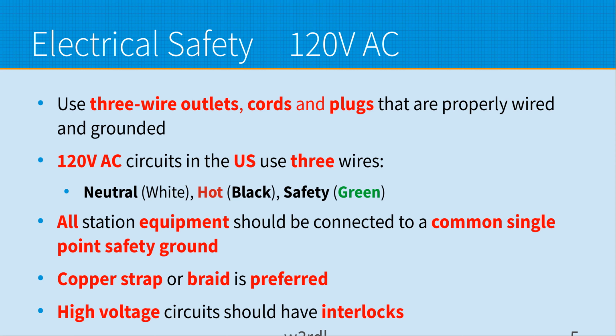So if the ground potential rises, everything rises with it, so there's no difference in potential, which is what's required for current to flow. So if there's no potential difference, there's no current flowing. You normally use either a copper strap, a braid, or heavy gauge wire to connect your grounds indoors. It's not recommended to use braid outside because it oxidizes and disintegrates. So you should either use copper strap or a very heavy gauge, at least 6 gauge or larger ground wire.